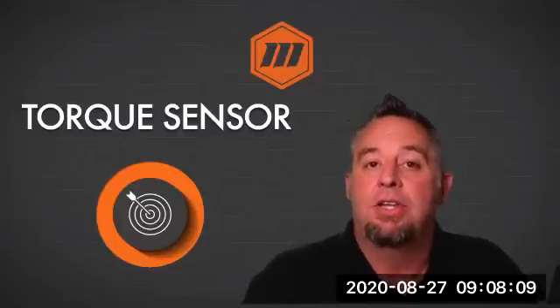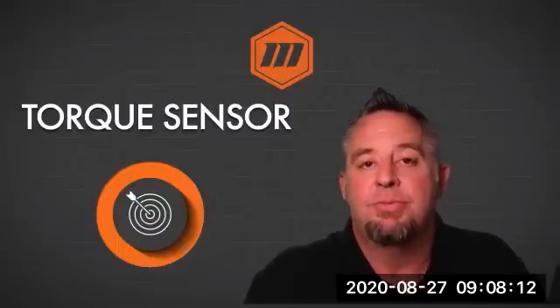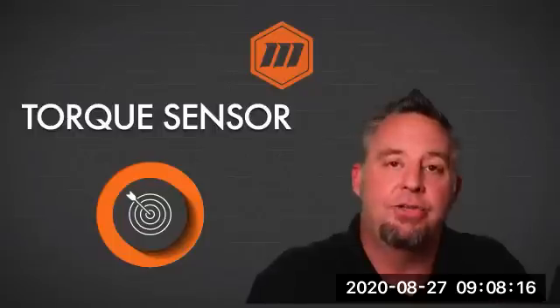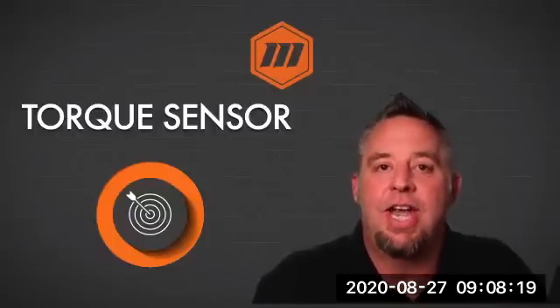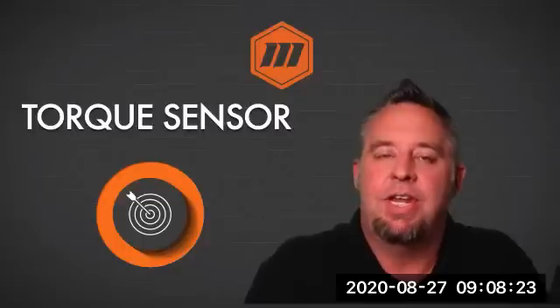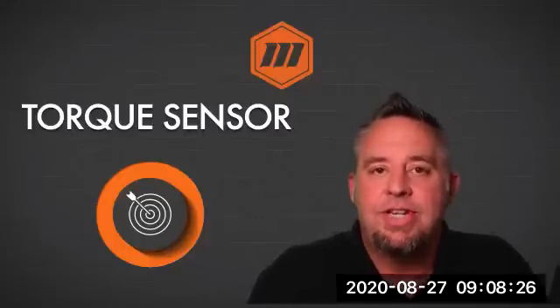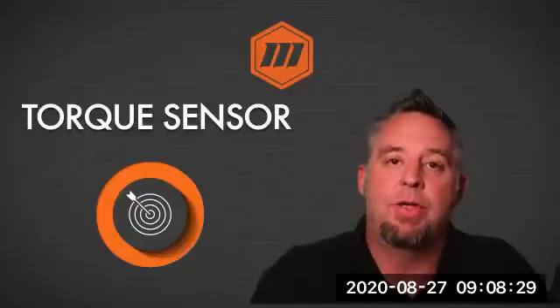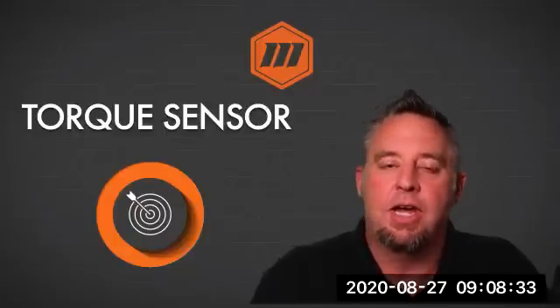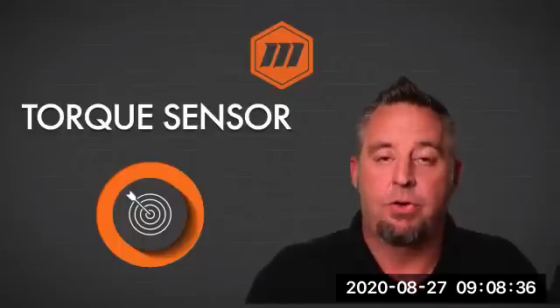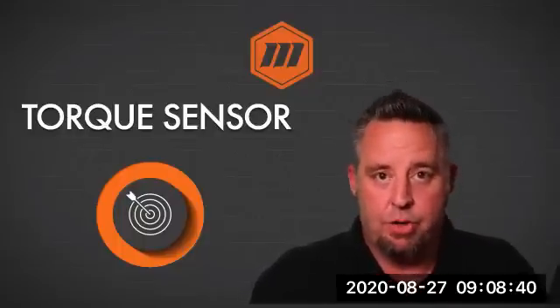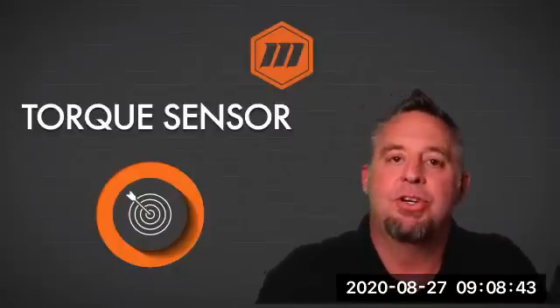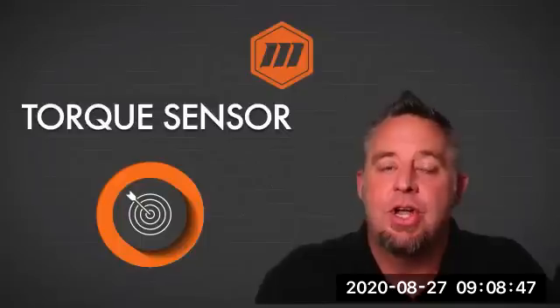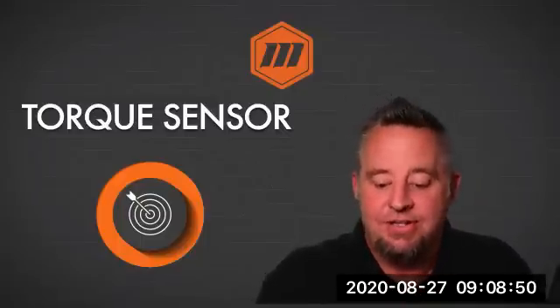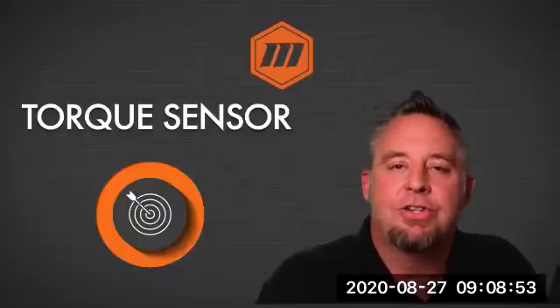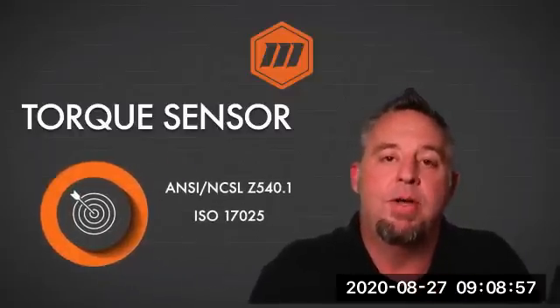Some torque sensors are built into an analyzer. Some sensors we can plug into maybe a handheld device, and you'll see some of that that I have here today. But when you look at the sensor itself, the accuracy that you may see on our website with our sensors, you will see a plus or minus 0.25% of full scale. Now that is not really great when you're talking about being able to measure throughout the full scale of the sensor.